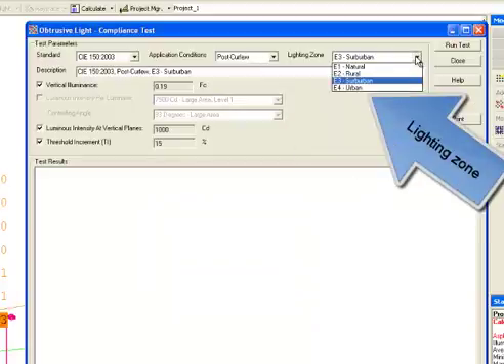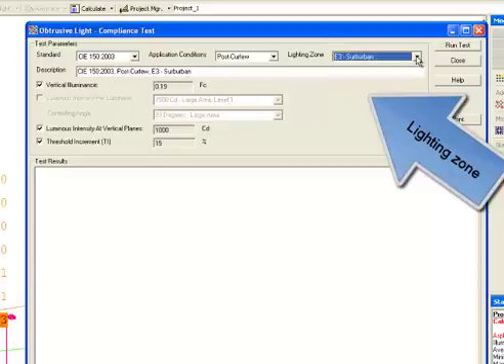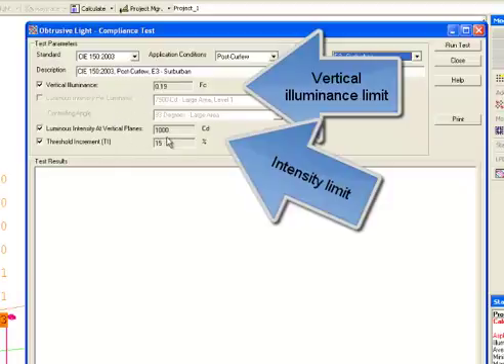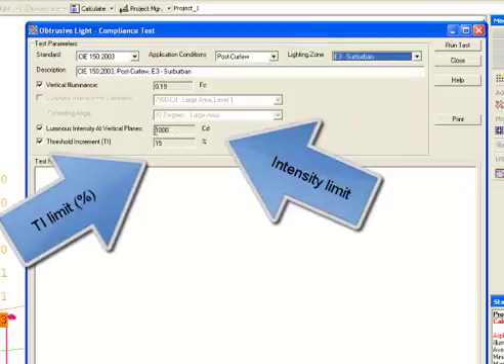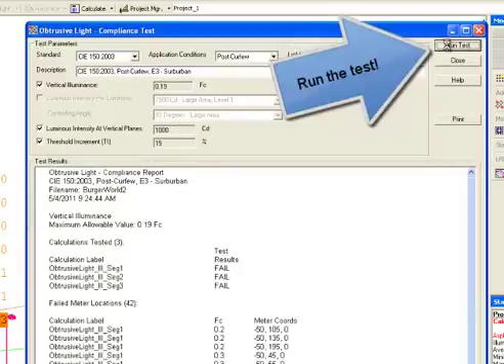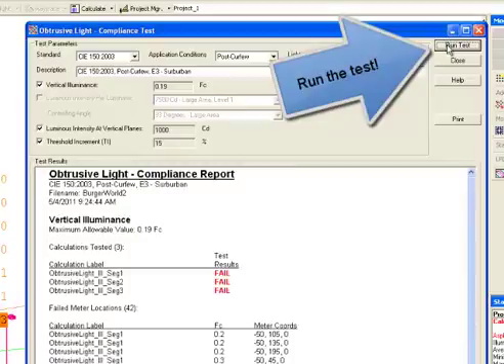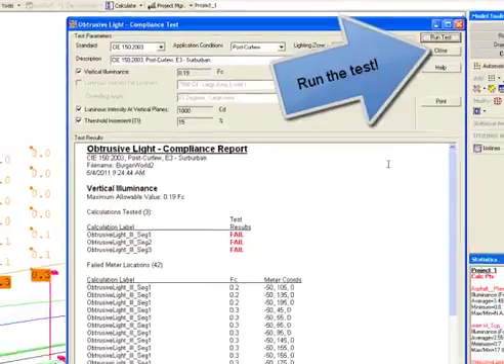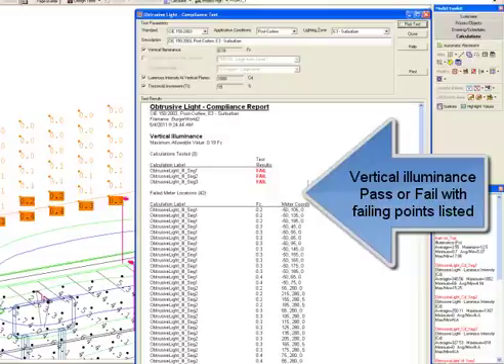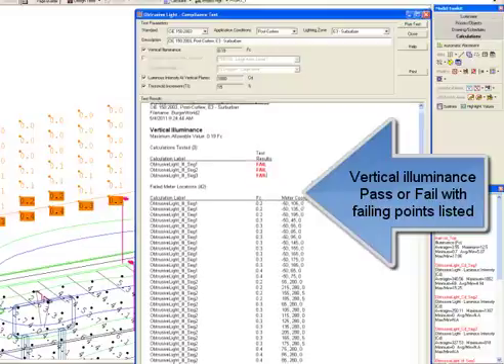Here are all of our specifiable limits per CIE 150 and AS4282. Post curfew, the lighting zone is suburban. Vertical illuminance limit, 0.19 footcandles. Intensity limit, 1000 candela. TI limit, 15%. Run the test. Vertical illuminance pass or fail with failing points listed.